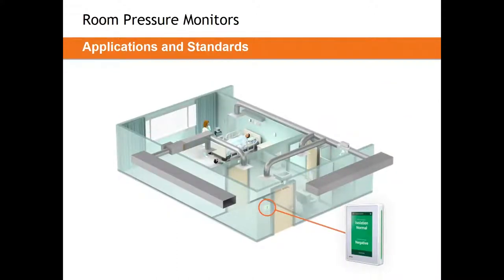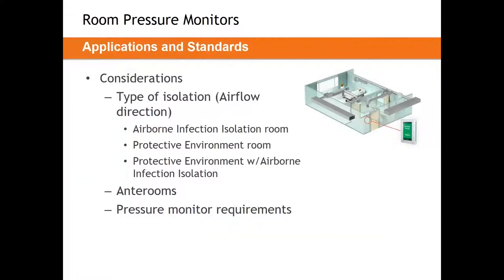The first application is the most simple: the hospital isolation room. These are fairly stable spaces that often act as patient rooms but have the capability to go into isolation mode. The air change rate is fairly modest at about 12 air changes per hour, temperatures are fairly standard, and these are fairly easy to control spaces — but we have a few different considerations.